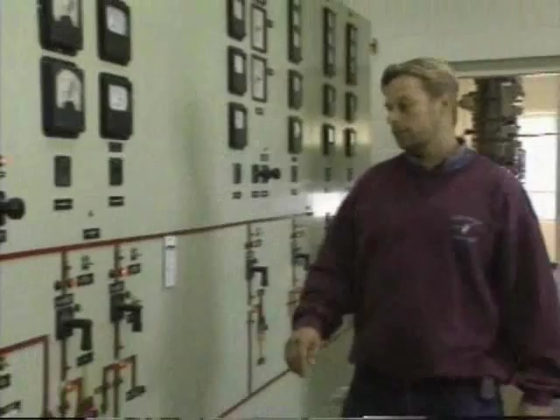Anything out of the ordinary starts with an alarm. The alarm comes to the dispatch center from SCADA, short for Supervisory Control and Data Acquisition. Circuit breakers automatically trip open, removing the line from service and sending an alarm to the control center. The dispatcher, using the SCADA system, will reset those circuit breakers by remote control and may operate them to see if they trip again. If they do, this confirms the line is bad and will need repairs.